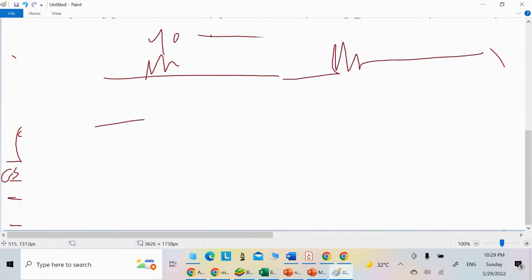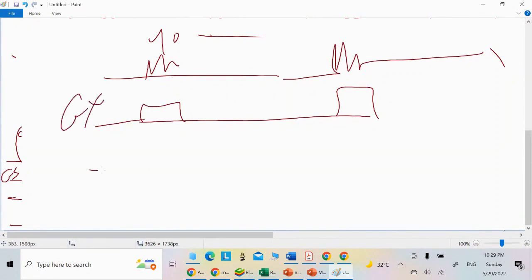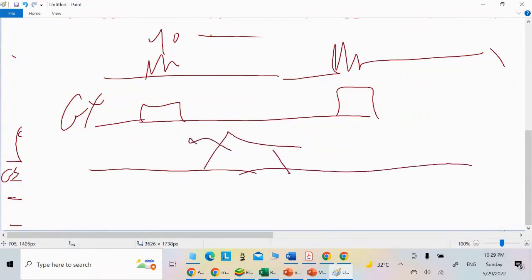With 90-degree slice selection and some 180-degree slice selection, when you give 180, you need to have a slice selection gradient to differentiate between the slices. Here, you will apply the phase encoding gradient. Okay, now record the frequency encoding gradient.